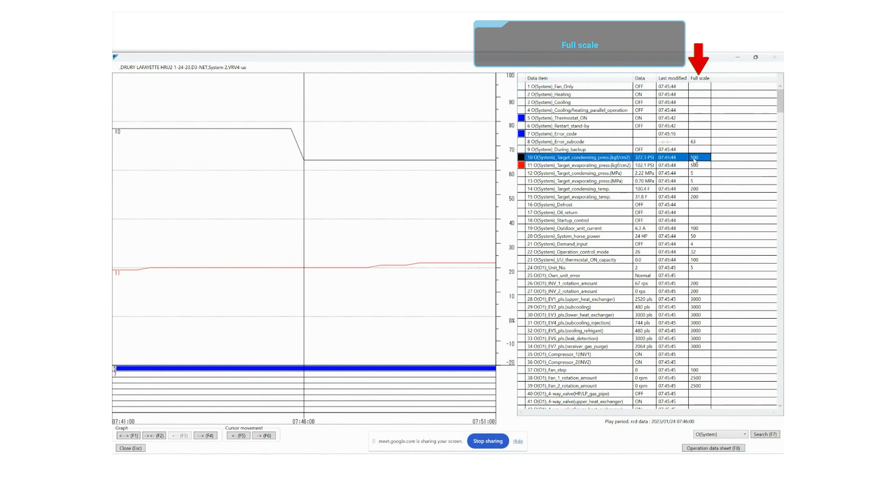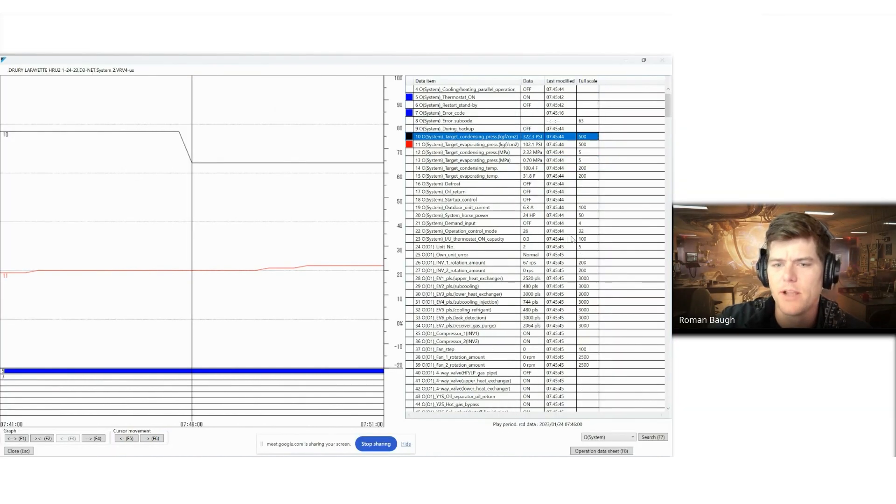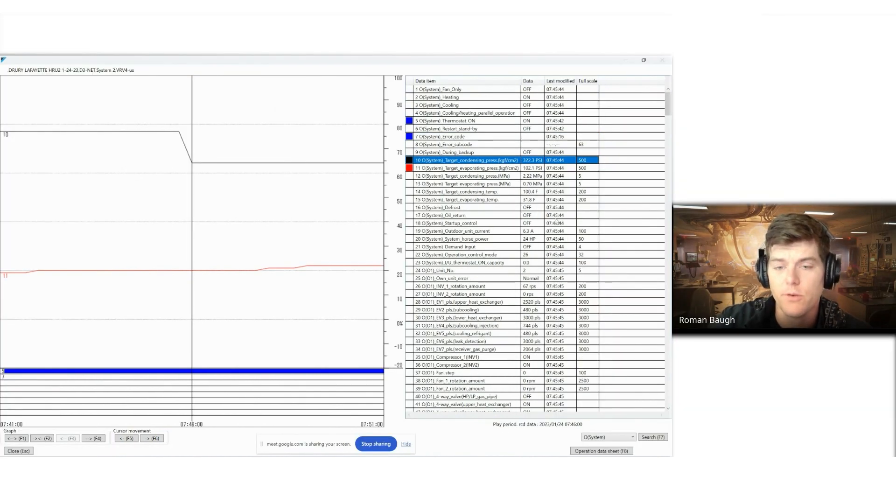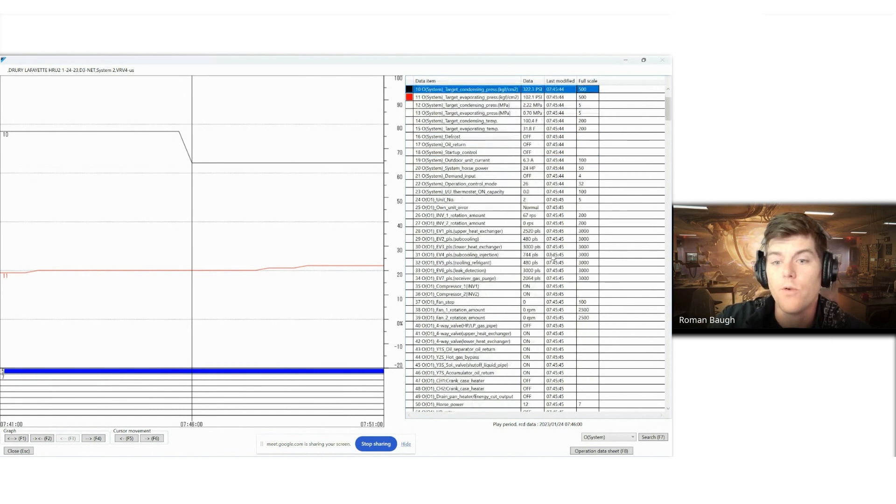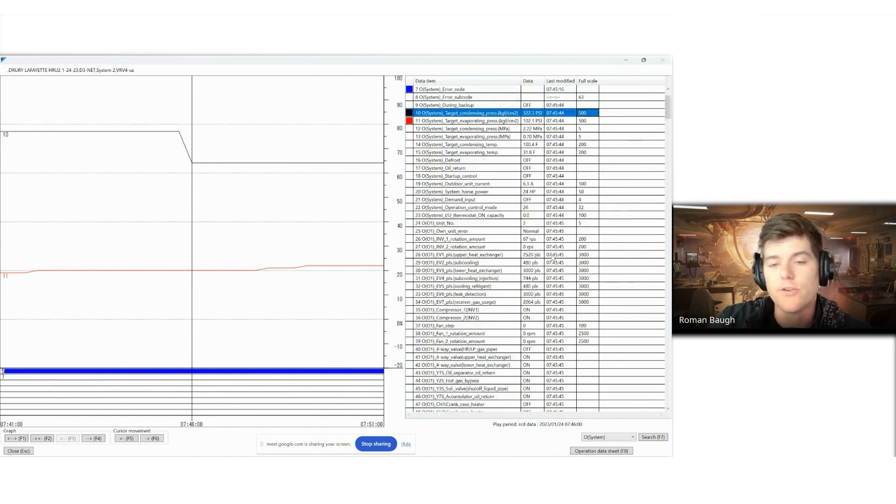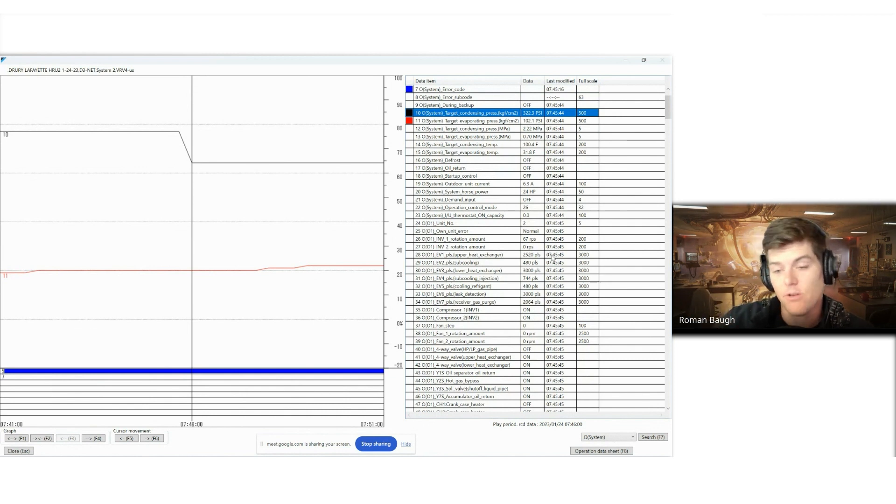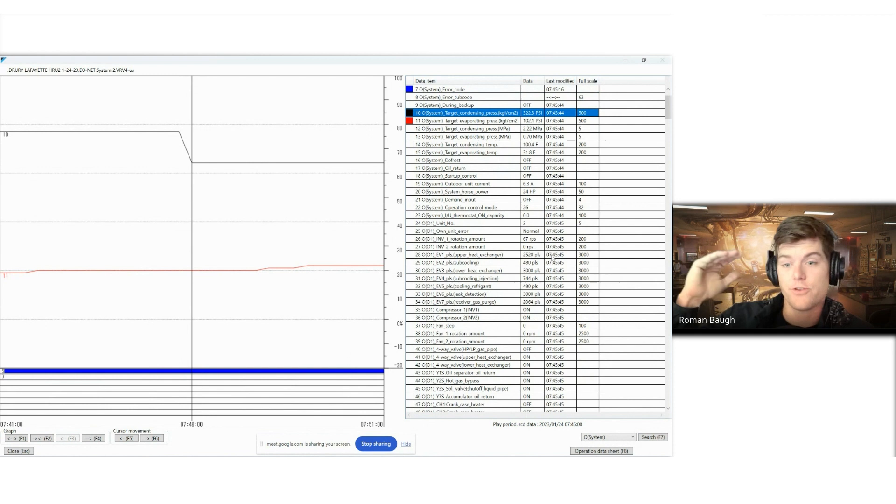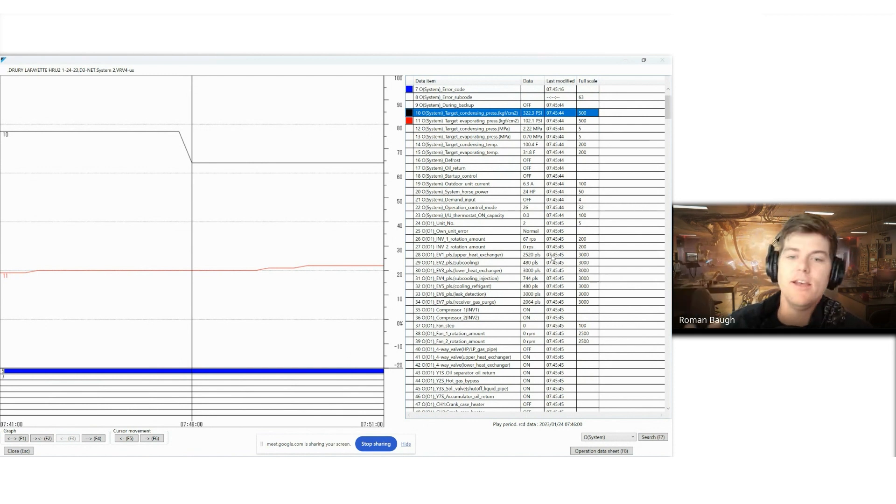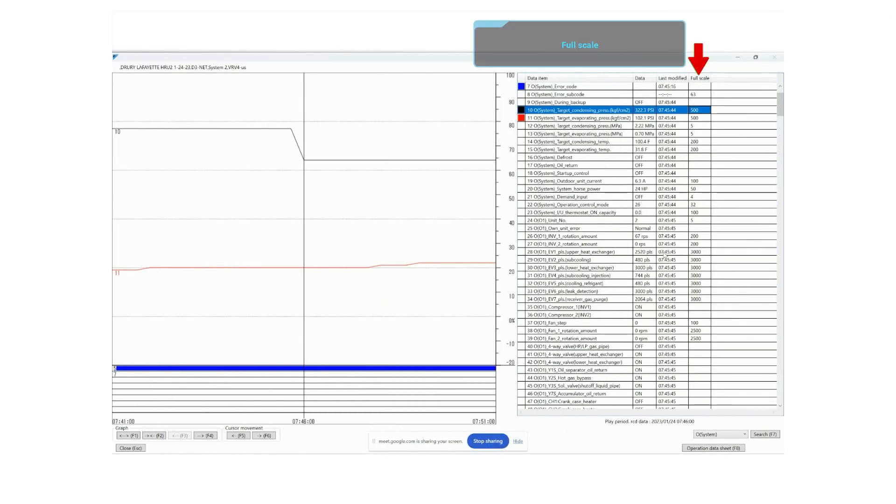So you'll notice here for target condensing pressure, the full top scale range of that is 500. This gives you perspective. If you're not familiar with VRV or VRF systems, you may not understand or know what your bottom threshold is, which is typically zero, but more so you wouldn't know what your top end threshold is. How wide open is my valve? So it says it's 200 pulses. Is that wide open? We can know that by looking at our full scale here on the right hand side and see that this valve pulses at 3000 is 100% open.